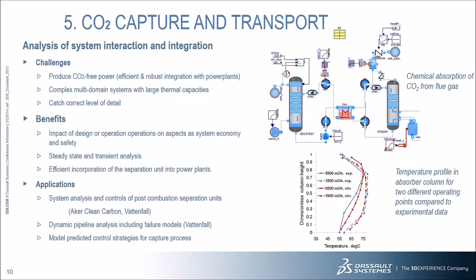The upper picture shows the model of a carbon dioxide absorption process. The solvent, an amine, is loaded in the absorber column with carbon dioxide from the flue gas stream. The gas is then stripped from the fluid in the desorber, separated from water, and further processed for storage. The energy for the process is extracted from the steam turbine of the power generation process, creating an interaction between the two parts of the system and their dynamics.